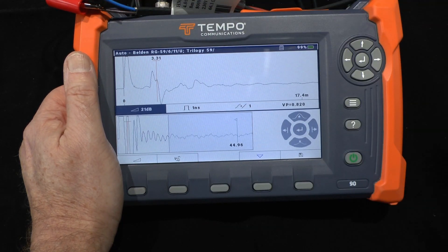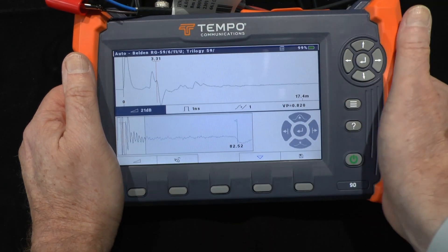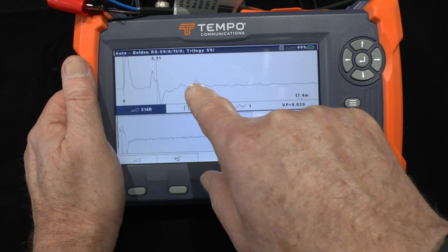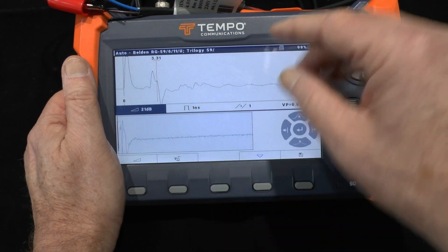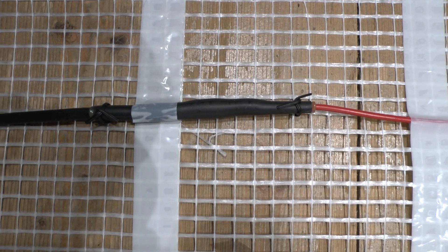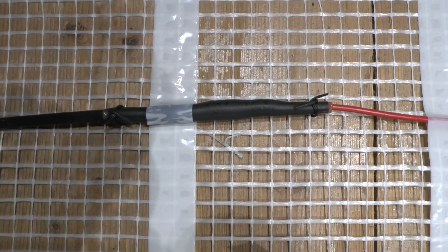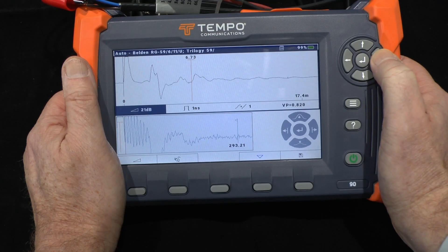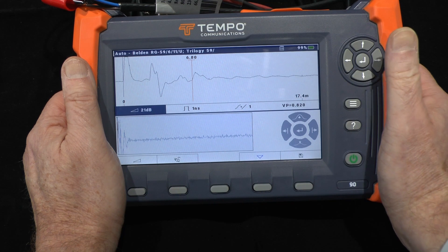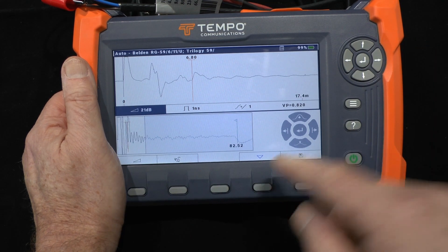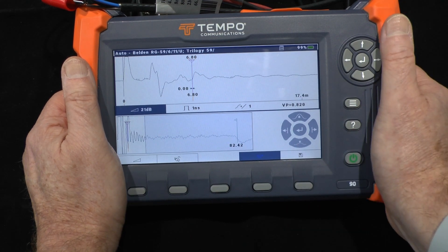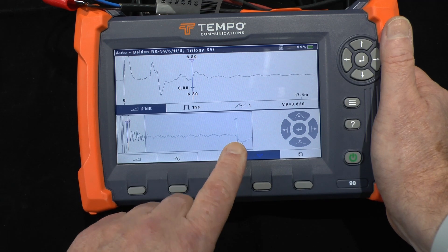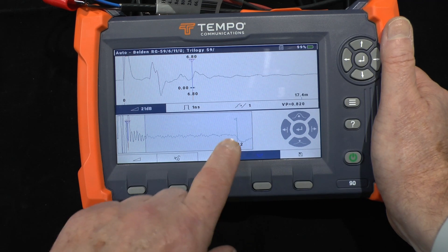What we can see here is the launch — the input cable to the heat mat — and then the heating cable beyond it. There is a transition of cable type just here. If I move my cursor to this point and place a marker, then in the overview trace down here we can actually see the end of the cable.